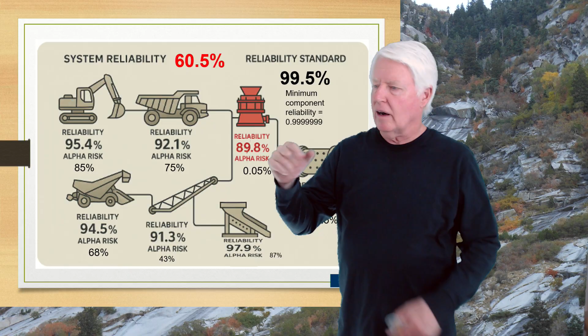And when that happens, the alpha risk is below 5%, which this one is, it turns red. And it tells you, hey, this is sending signals that it's going to fail sometime in the reasonable future. And it'll have a confidence interval to give you an idea of how much time you have. Okay, but it will do this on every sensor. So if this is your asset, you'd click on it, it'd have all the sensors on there with associated alpha risk. And if any of those alpha risks go below 5%, 5% or below, it will change it to red.